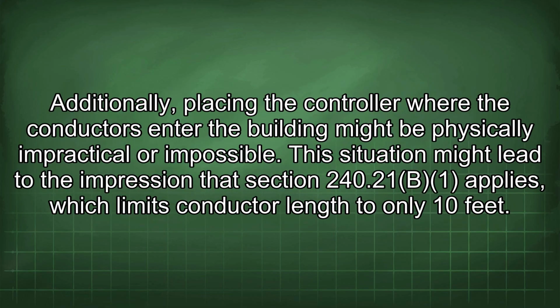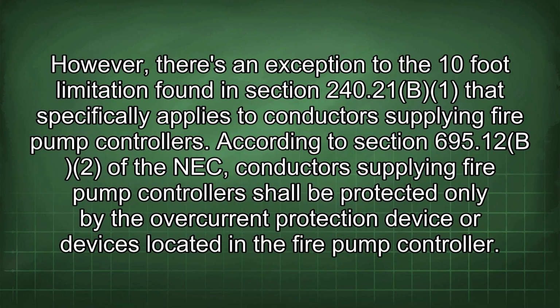Additionally, placing the controller where the conductors enter the building might be physically impractical or impossible. This situation might lead to the impression that Section 240.21(B)(1) applies, which limits conductor length to only 10 feet. However, there's an exception to the 10-foot limitation found in Section 240.21(B)(1) that specifically applies to conductors supplying fire pump controllers.